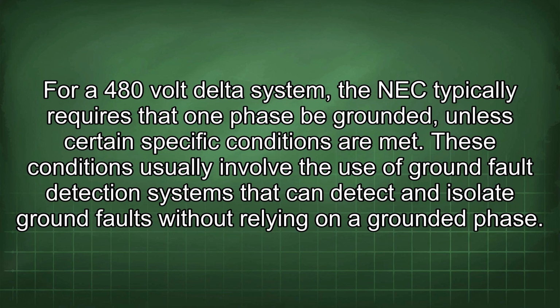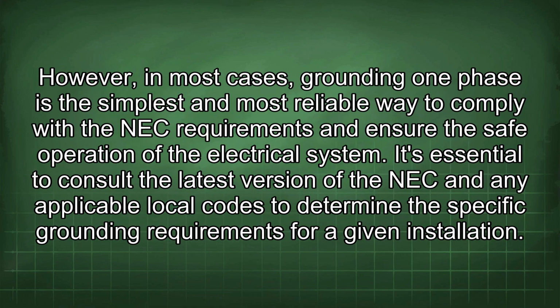These conditions usually involve the use of ground fault detection systems that can detect and isolate ground faults without relying on a grounded phase. However, in most cases, grounding one phase is the simplest and most reliable way to comply with the NEC requirements and ensure the safe operation of the electrical system. It's essential to consult the latest version of the NEC and any applicable local codes to determine the specific grounding requirements for a given installation.